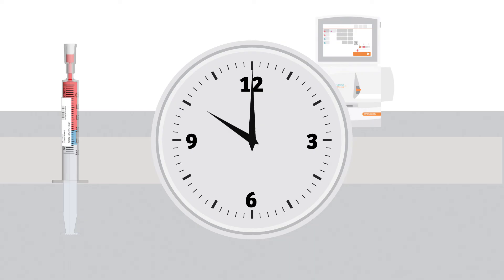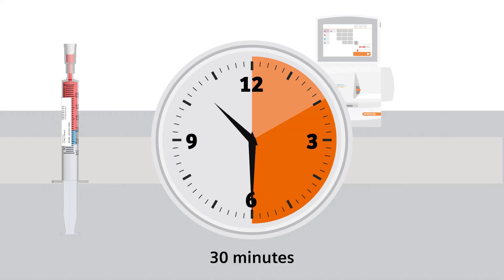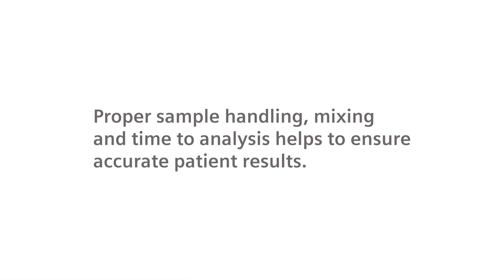According to the CLSI guidelines, blood gas testing should be completed within 10 minutes and not longer than 30 minutes after drawing the sample. If testing is delayed longer than 30 minutes, samples should be placed in an ice slurry and will require additional mixing prior to analysis. Dispose of the syringe according to the hospital guideline. Proper sample handling, mixing, and time to analysis helps to ensure accurate patient results.